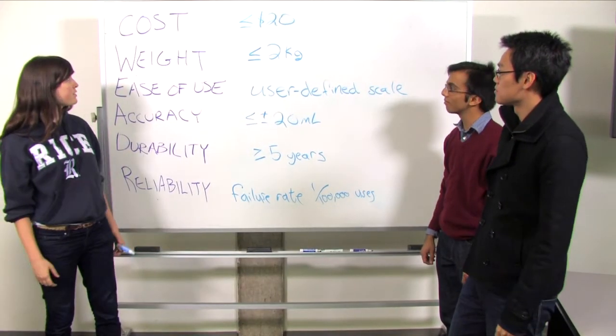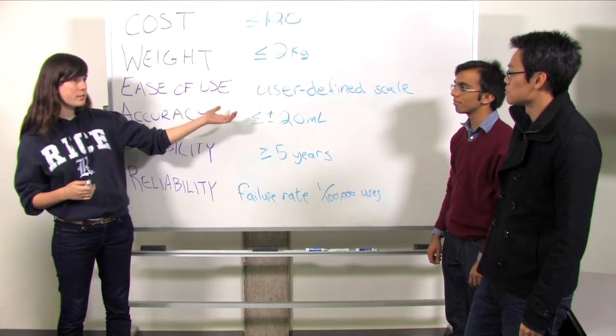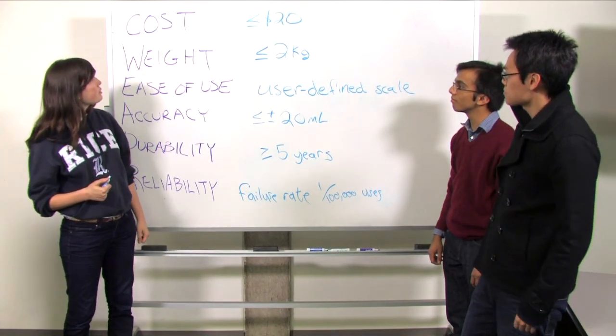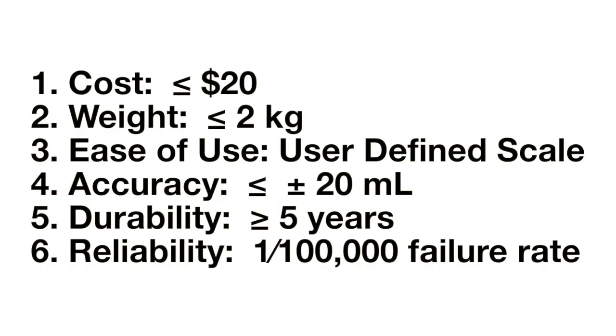So what we've done is we've taken our objectives and we've turned them into measurable design criteria that we can use when making decisions about how we're going to engineer this device. So we said we want our cost to be less than $20 and the weight of each device to be less than 2 kilograms. And when we came to ease of use, we thought it would be more suitable to have a user-defined scale. And when we came to accuracy, we wanted something that was under plus or minus 20 mils instead of an actual percent of IV fluid dispensed. As for durability, we decided on something that lasts more than five years. And for reliability, we quantified that as a failure rate of less than one failure per 100,000 uses. Thank you.